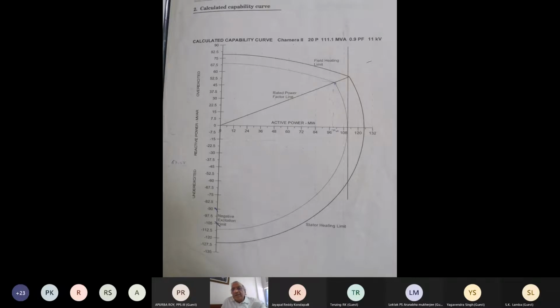Whereas in the under-excited mode there is stator overheating due to excessive leakage flux in the end region of the generator. So there is end region overheating of the generator during under-excited operation. So these two are different types of phenomena. One is related to the excessive leakage flux in the under-excited mode, whereas in the over-excitation mode it is a thermal limit of the current carrying capacity of the exciter winding and also the generator stator winding.